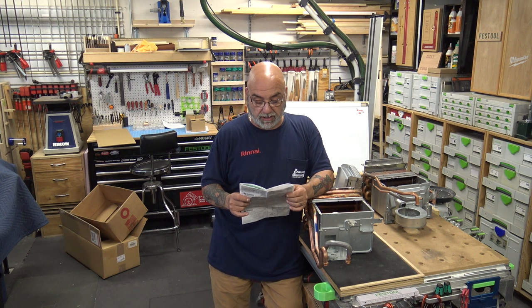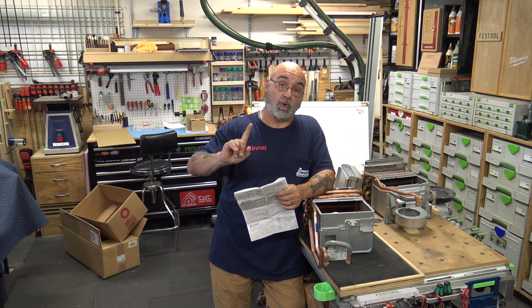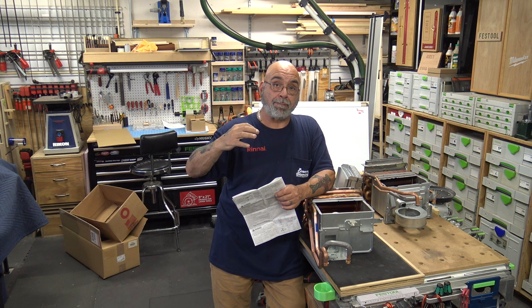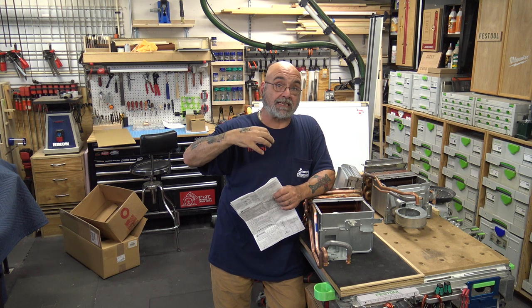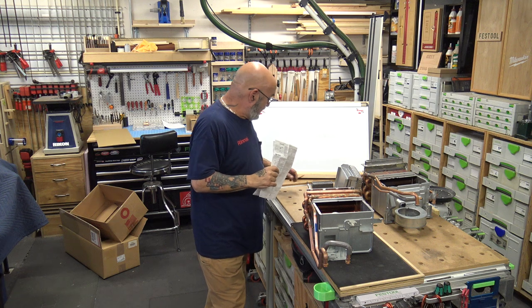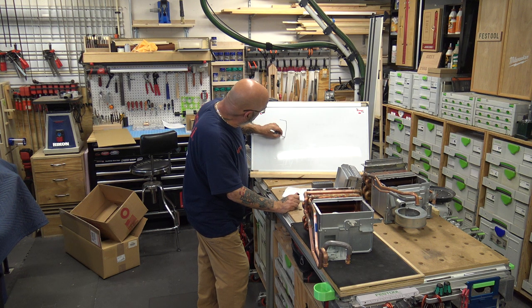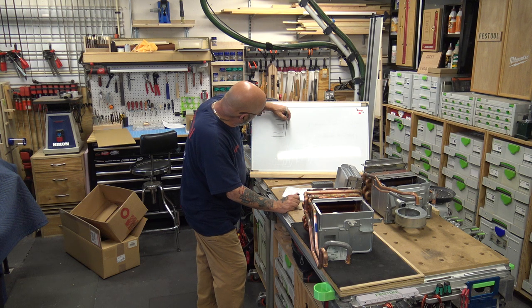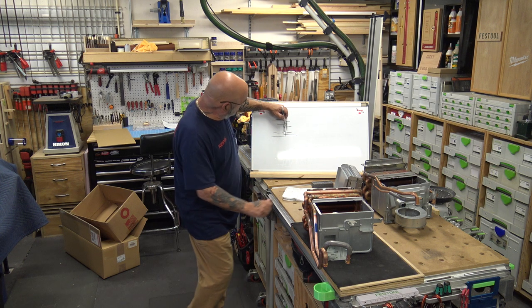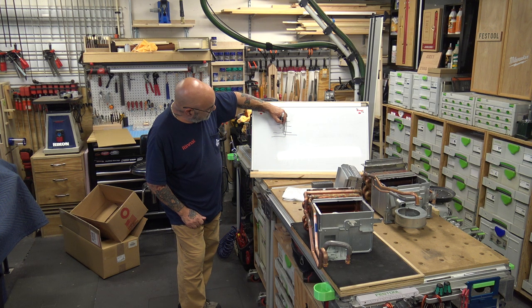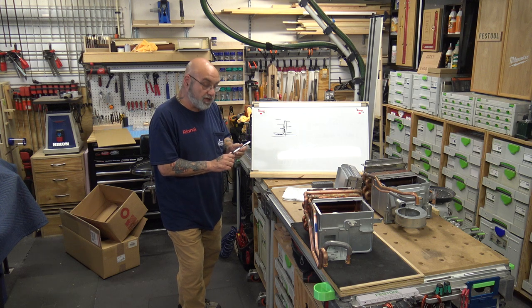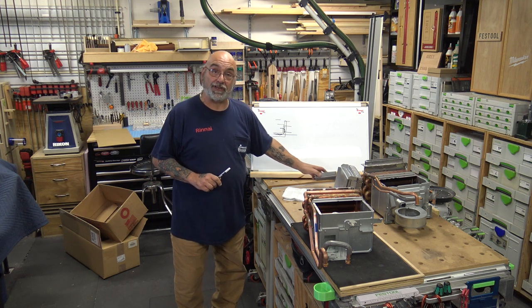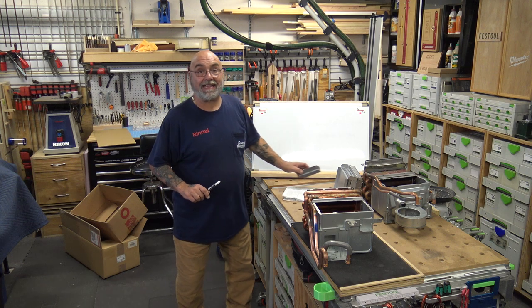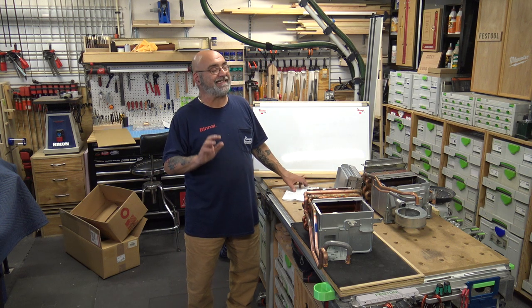Check all vent components for proper connections. That could also cause issues—if it's not pushed in all the way, you will be drawing the carbon monoxide back around. If your connection is not all the way in like this, you will be drawing the carbon monoxide back around into your fan again, and you're going to be using carbon monoxide for combustion. Now that will make another annoying, obscene sound.